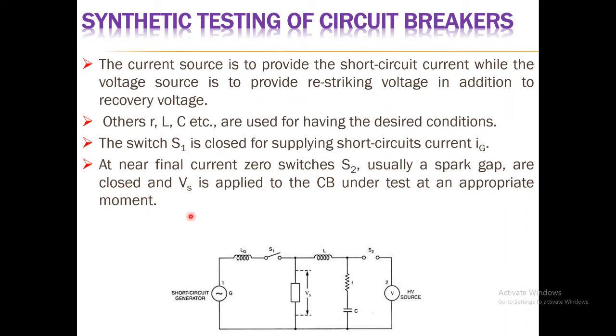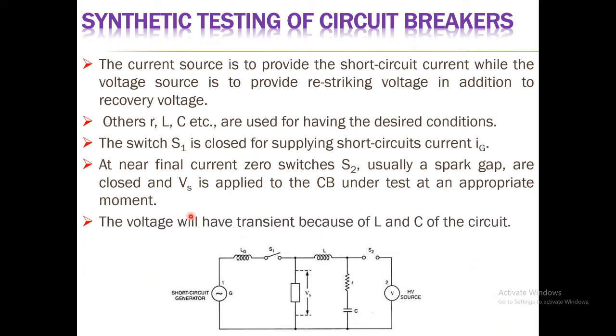At near final current zero, switch S2, usually a spark gap, is closed and the voltage VS is applied to the circuit breaker under test at an appropriate moment. This is the basic flow of conducting a synthetic test. The name 'synthetic' is given because two different sources are used — the composition of two different sources — and the voltage will have a transient component due to the L and C of the circuit.